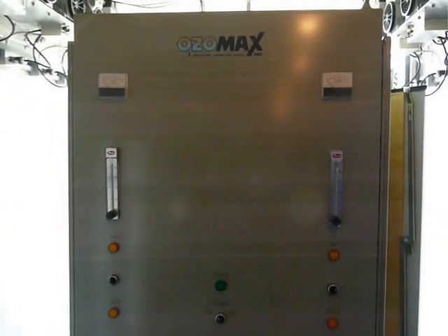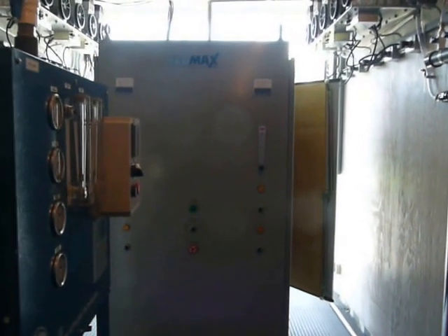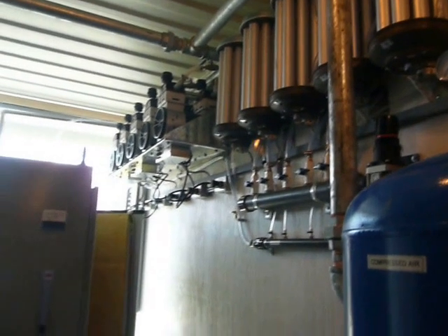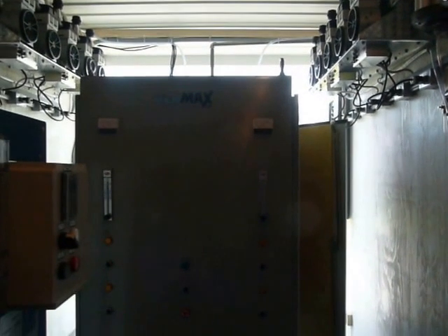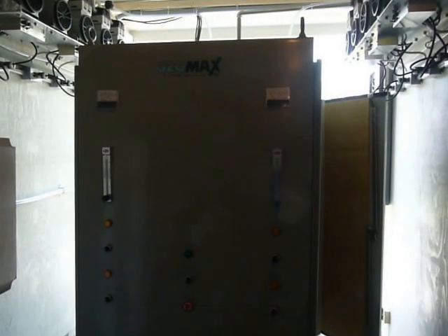Once the ozone is produced, it is directed to the other section of the container, which is basically the water treatment section. Before we leave this area, though, I'd like you just to take a look at the compressors and the oxygen concentrators that provide concentrated oxygen to the ozone generator. The reason why we use oxygen as feed is that when we use oxygen feed as opposed to air feed, the ozone production capacity of the same ozone generator doubles. And the concentration of ozone produced is much higher, which facilitates greatly the mass transfer of ozone from the gas phase to the water phase.